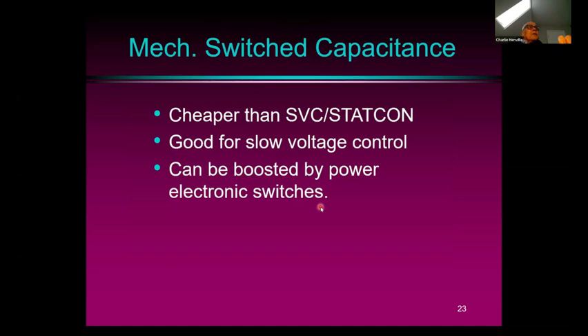So mechanically switched capacitors are much more commonly used, and I shouldn't say great, but it's an economical way to increase the amount of power that you can deliver, as we saw at the beginning, just by boosting the voltage at the delivery point. So these mechanically switched capacitors are cheaper, more economical than static VAR compensators or static condensers.